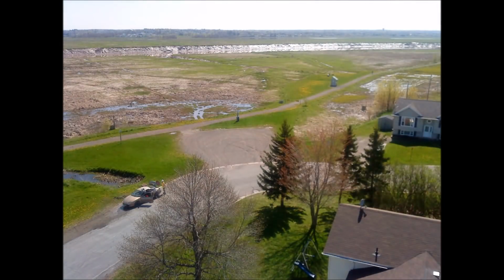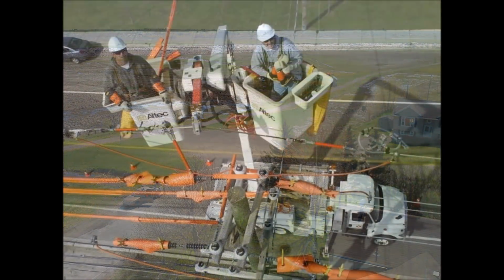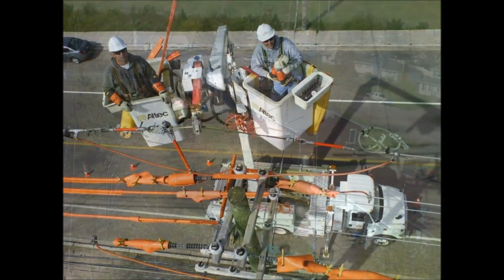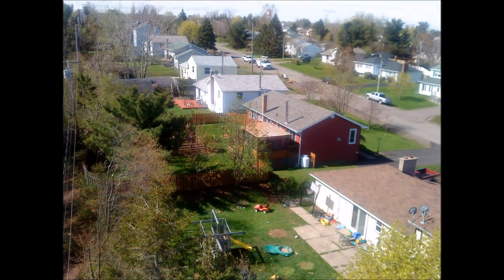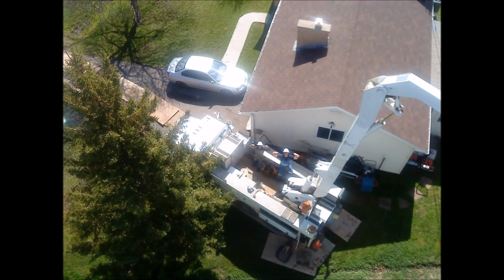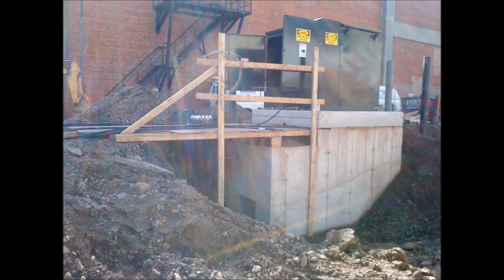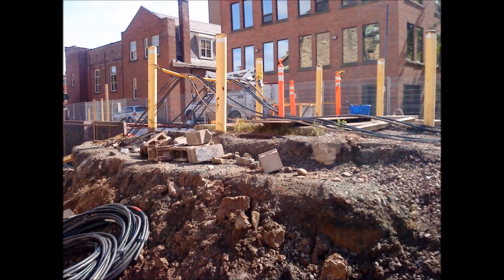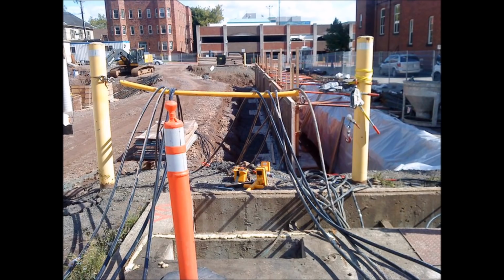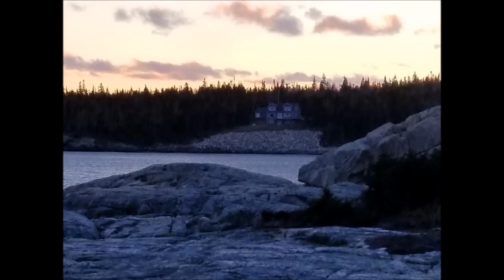Such work can also not be performed while the cable is energized, unlike working on overhead conductors. In a more densely populated area, this process would have already been completed as the system was put into place. That way, houses can tap onto the transformers as they are built. I've touched only briefly on the pros and cons of underground power lines, and when applied correctly, they are great. But for some, it simply does not make any sense.